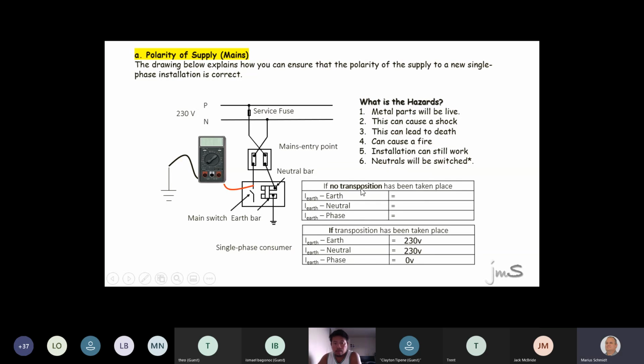Now, if everything is fixed, look what it says here. If no transpositioning has taken place, what are you going to measure between earth and neutral? Independent earth and earth. Independent earth and neutral. Independent earth and phase. 230. Now, I want to sit back, relax, and tell you something interesting. You will get questions like this. If there was transpositioning, you're going to get 230 to the wrong areas. If you get 0, 0, 230, that's what you want. You don't want 230s between two different places. Is that clear to everybody? If there's one test you must do, it will be this test.